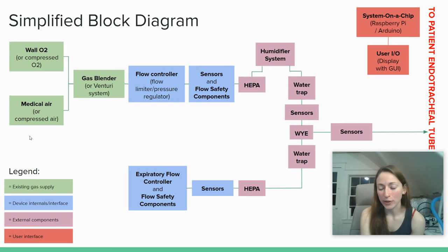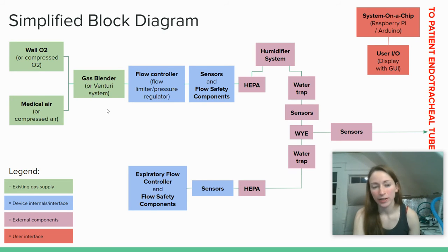Here again, at the wall of the hospital, we're looking at the existing gas supply in these green blocks. We have the wall O2, or compressed oxygen if you're in a field hospital setting, as well as medical air supply. These may come natively from the wall, and if so, they're supplied at approximately 50 psi, and they may go to an existing gas blender. If you don't have a gas blender, there are some pretty nice low-cost solutions involving Venturi mixers. With a single Venturi mixer, you can get up to 50% gas blend mixing, or you can have a dual Venturi system. This is a nice area where people can consider lower cost solutions to existing hardware.